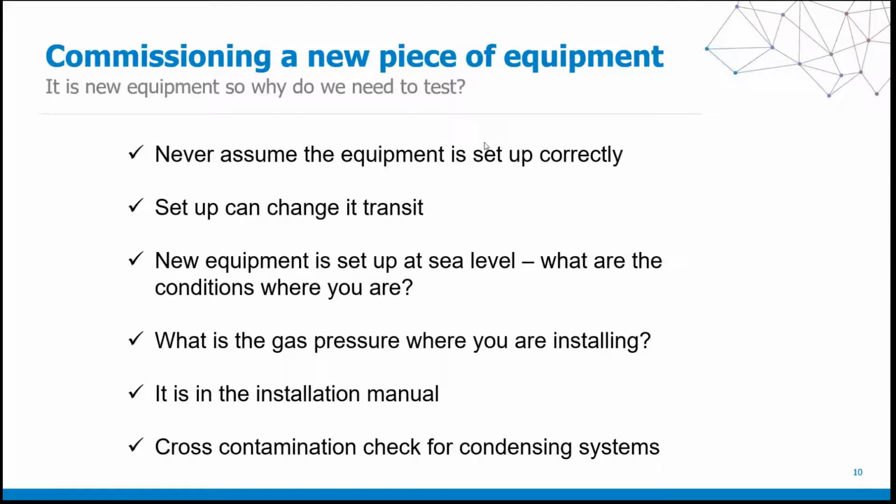Cross-contamination check for condensing systems. If you're installing a brand new condensing piece of equipment, do you have cross-contamination? And are you even aware that that is something you can check using a combustion analyzer?